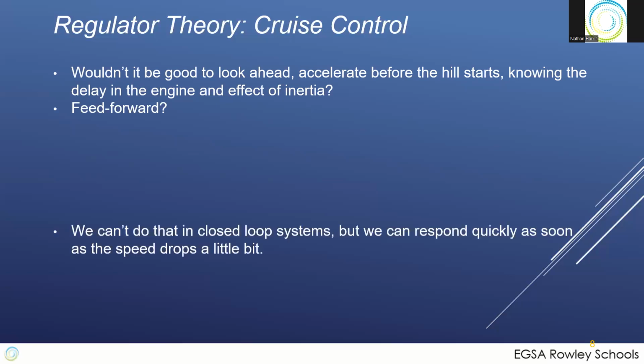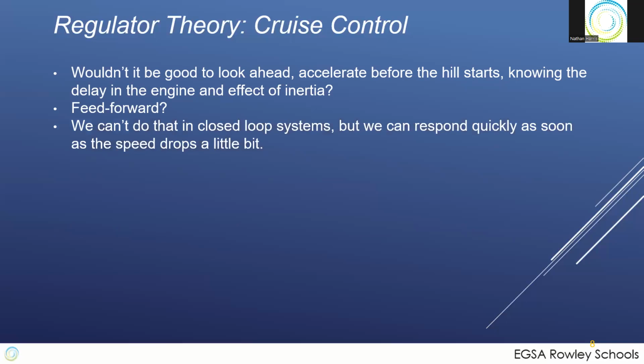Well, we really can't do that in our closed loop systems. We can respond as quickly as possible, but we really can't feed forward. There are technologies that are looking at doing that in naturally resonant systems, for example, MRIs. That thump, thump, thump of an MRI just plays on generators. And so they've been able to do things in the system because we know that's going to continue for a period of time. So with that thump that happens, we can sometimes bump the gain. We can increase the reference a little bit, knowing that we're going to have more problems in the near future as this MRI continues. So feed forward isn't really used very often. It's a very specialized technique, but really can't do it in everyday systems.